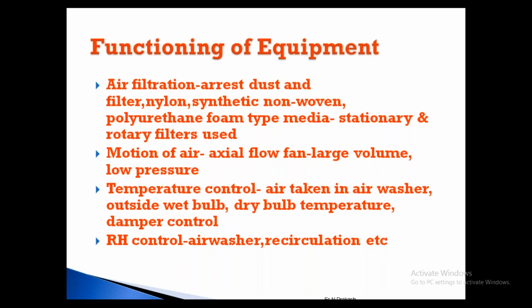Then there is the motion of the air, how the air moves inside your distribution, as already explained, and how it is distributed through the fan. We'll go to the fan later. A large volume of air at low pressure, so axial flow fans are used. As for temperature control in the air washer, how the outside maximum is controlled, your temperature is controlled through damper control, and RH is controlled by recirculation of the water with the pump system. The RH can be increased, but to decrease it you spray less, it works with less efficiency, and you will get less RH.